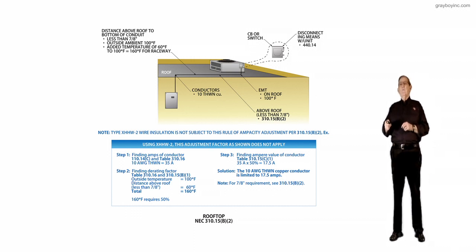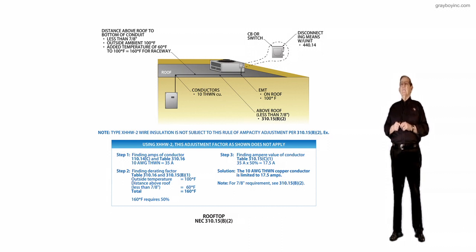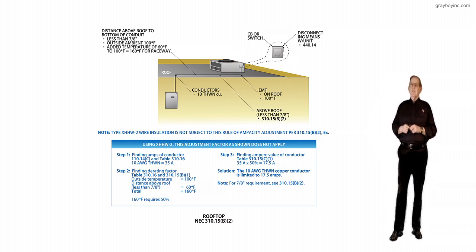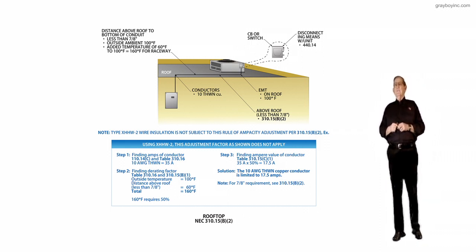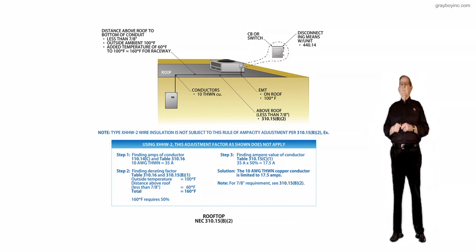Notice first of all, we have in the illustration pointing to the conduit on the roof. It's EMT, and on the roof it's 100 degrees Fahrenheit, selected from the ASHRAE handbook. That's the only place you could really get it, is from the ASHRAE handbook, as recommended by the NEC.